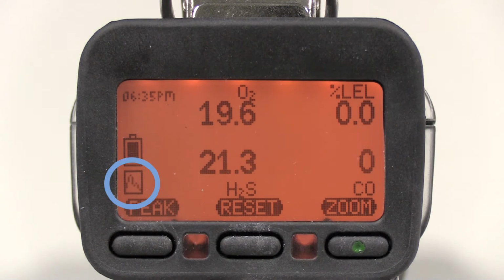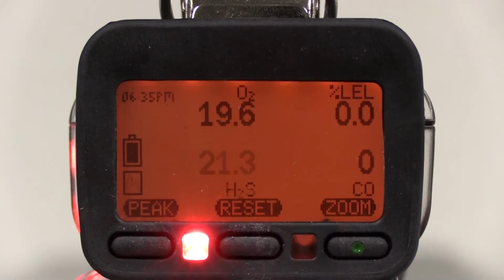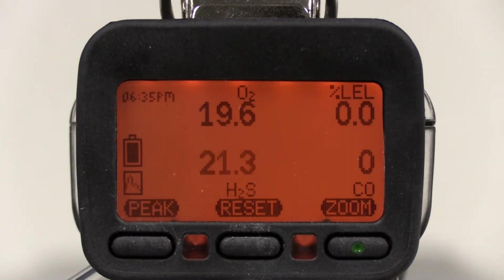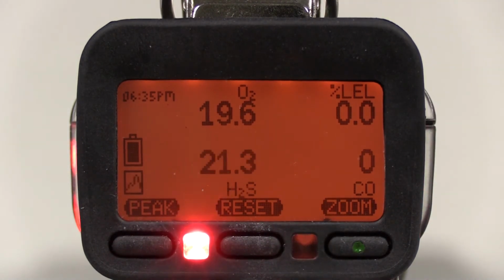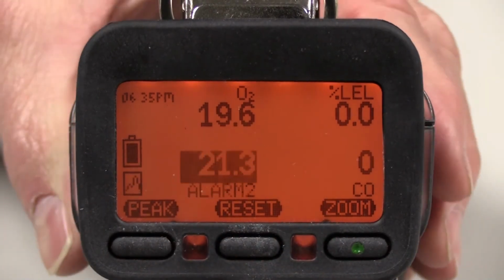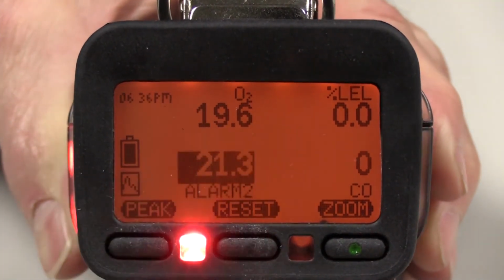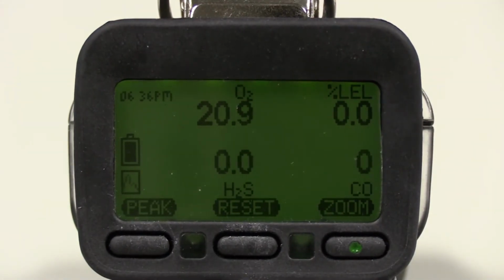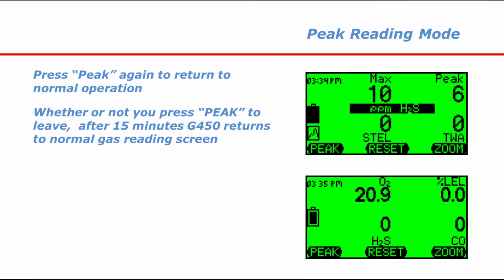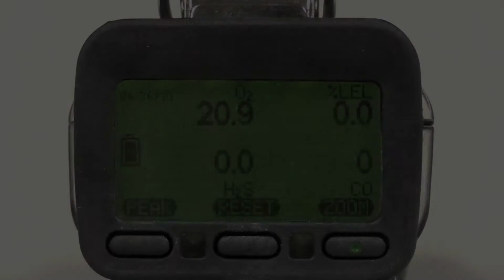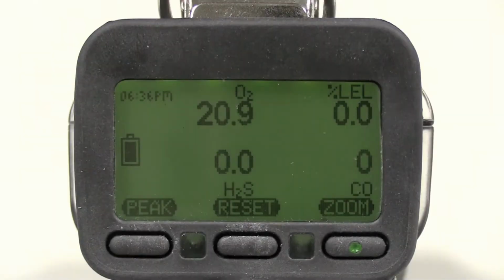A common use for peak hold operation is sampling the atmosphere during confined space pre-entry procedures. The instrument can be tied onto a lanyard and lowered into the space. The display will stay locked on the most significant reading until you press the reset button. The instrument should not be left in peak hold mode for extended periods of time. Press the peak button again to leave the peak hold mode and return to normal operation.